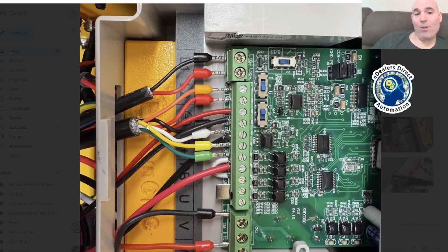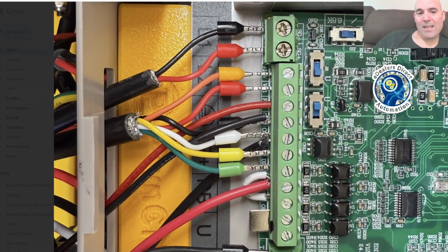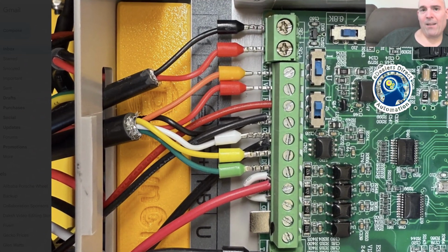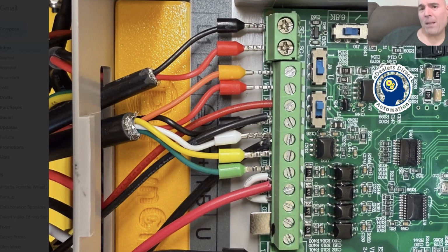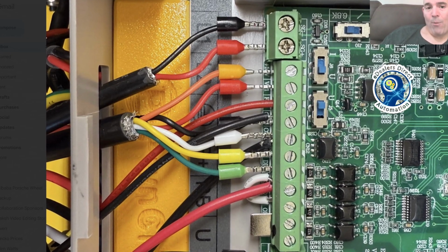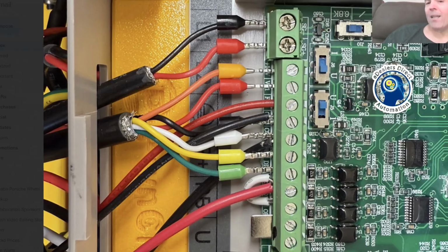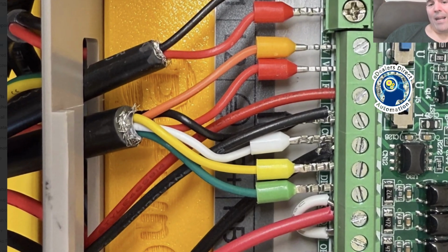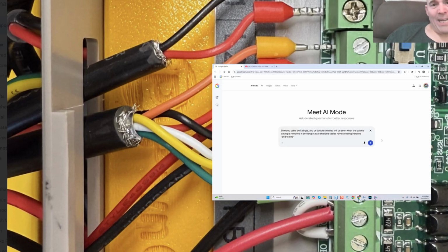Okay, I have no idea why they would use pieced together cables here that are shielded, yet the cable that he ran to his spindle is not. And we can see that right here. And this is exactly what you would see on a shielded cable, in that when the casing is removed, you would see the shields present upon any casing removed, because when cables are made in rolls, the shielding is applied at the second it's made, meaning from the beginning of the roll to the end, it is installed.